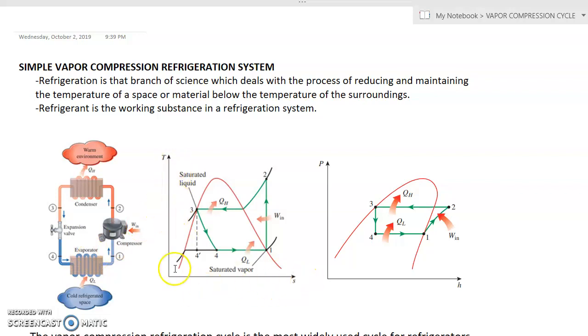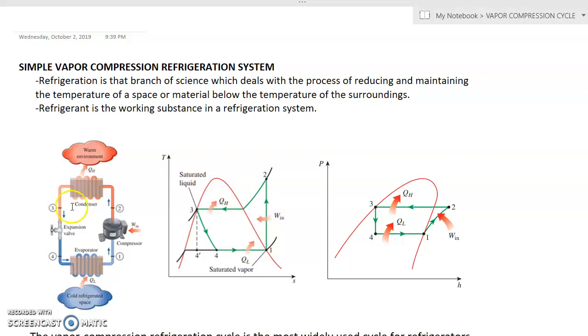If we plot these on the T-s diagram, the red curve is the saturation curve. Ideally, we assume that point one is the saturated vapor, and point two is superheated — that is the state leaving the compressor. Point three is saturated liquid, and point four is a wet vapor mixture. This is the ideal process: one, two, three, four.